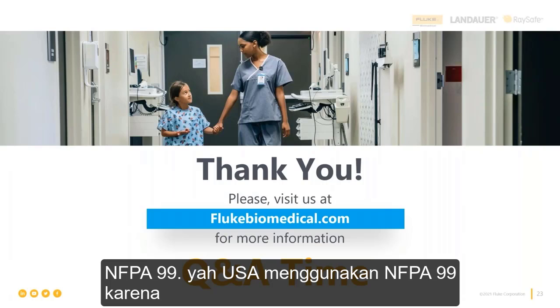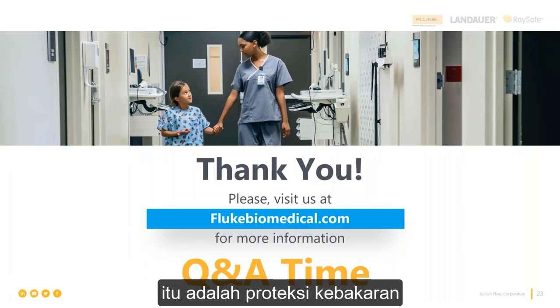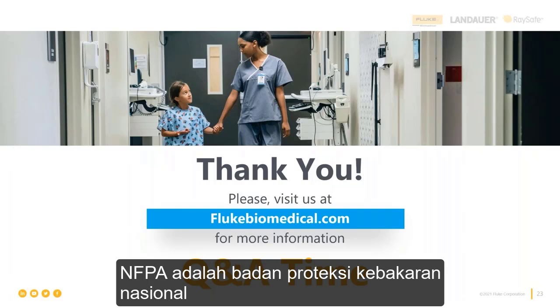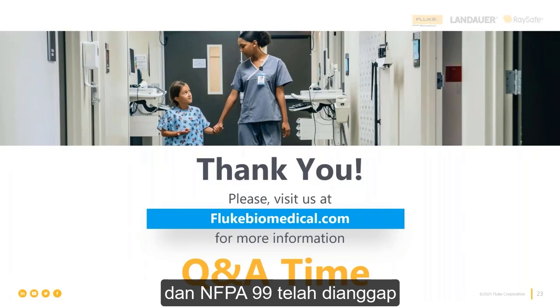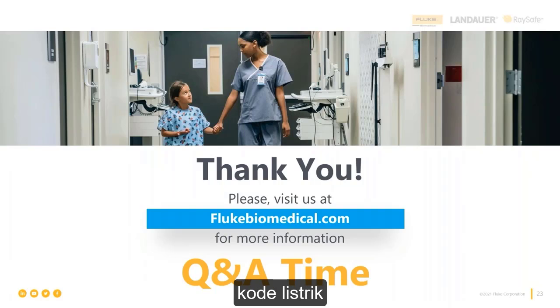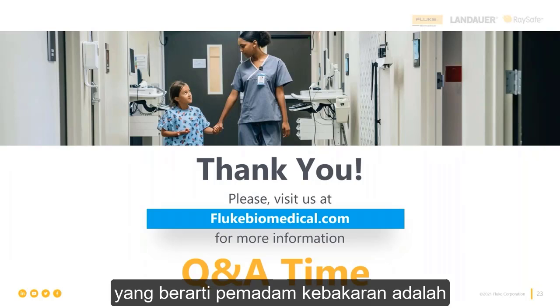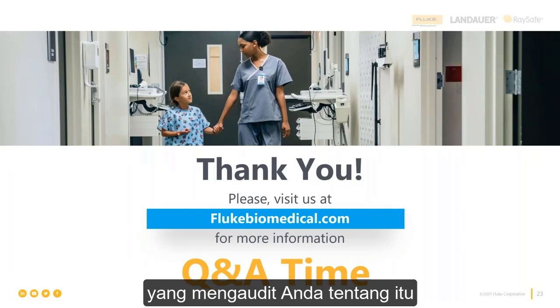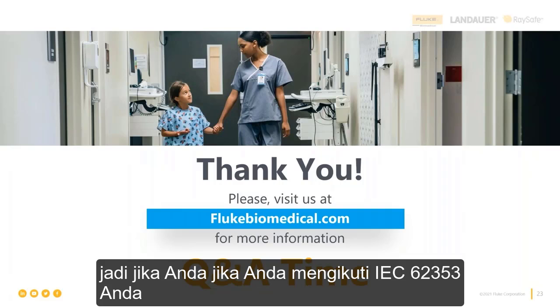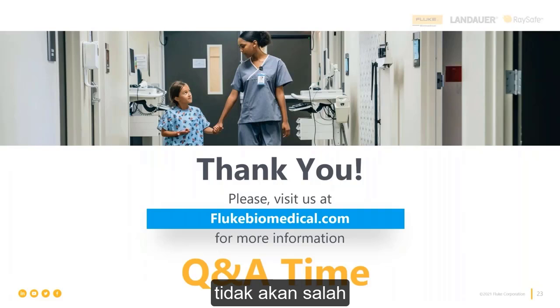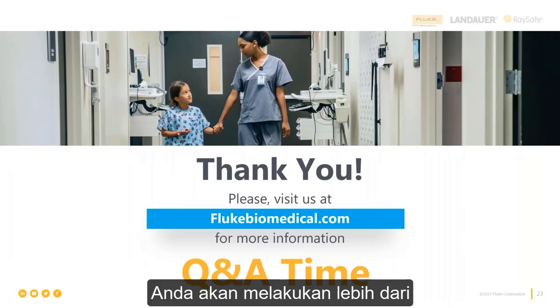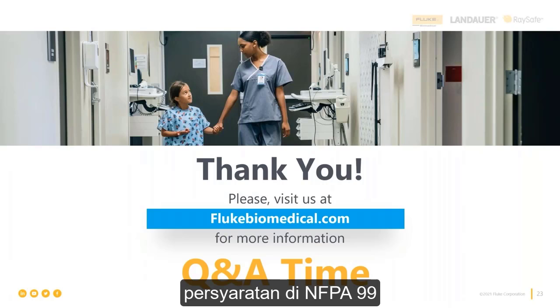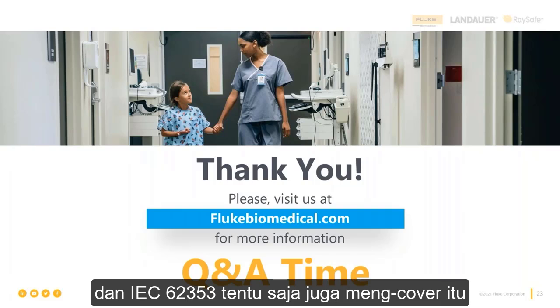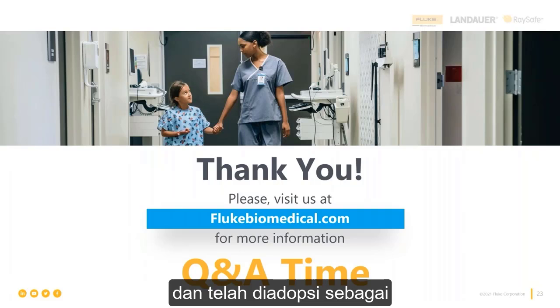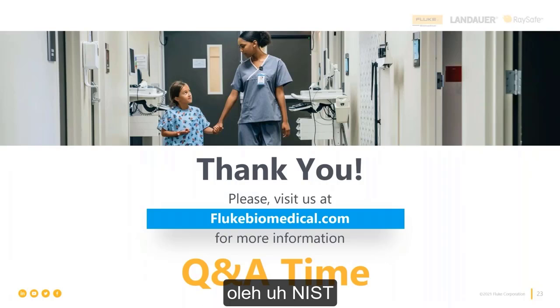Well, USA uses NFPA 99 because that is a fire protection standard. NFPA is the National Fire Protection Association. And NFPA 99 has been deemed an electrical code, and so it is enforced as an electrical code. That means the fire marshal is the one that audits you about that. So if you followed IEC 62353, you would not be wrong. You would have more than covered the requirements in NFPA 99, and IEC 62353 certainly does and has been adopted as a United States electrical safety standard by NIST.